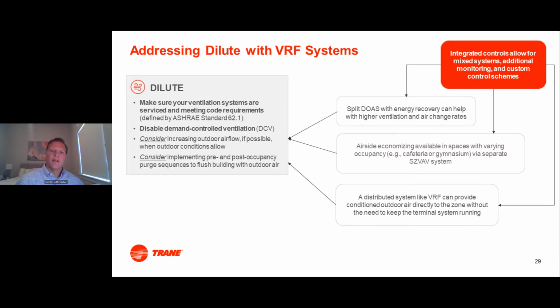And so you're going to have similar results as to how much outside air you're going to be bringing in for your occupants. When we're addressing the challenges of this pandemic, one of the ASHRAE recommendations has been to disable demand control ventilation. There's also been commentary around considering increasing our outdoor airflow if possible, and potentially running your ventilation system longer than your building occupancy. We call that a pre and post occupancy purge. Initially, that was focused on 2 hours before and 2 hours after occupancy. There's now some flexibility on how to reduce that amount of time depending on your system type.